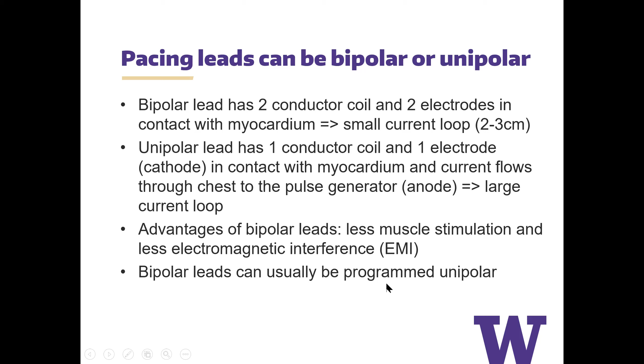The advantage of the bipolar leads is that there's less muscle stimulation and less electromagnetic interference, again because the bipolar circuitry is very small. Bipolar leads can also usually be programmed unipolar, so there's that advantage too. If you ever want a unipolar configuration, you can just program it that way.